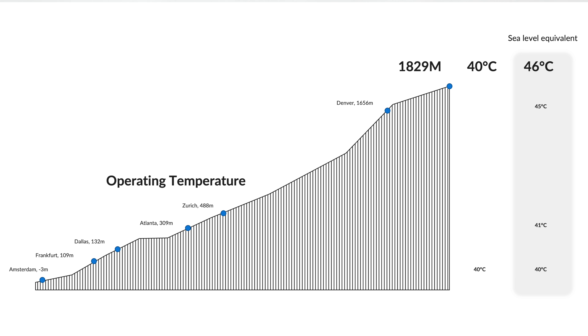The second parameter that influences every single electronic component is the elevation, for a simple reason: cooling capability is a function of air pressure, and therefore altitude. We use a simple rule of thumb to say that 1000 feet (around 300 meters) is equivalent to one additional degree Celsius at sea level. Consequently, to support a system at 1800 meters of altitude, you need to test it at maximum temperature plus 6 degrees — in our recent routers, that's 40 + 6 = 46°C.